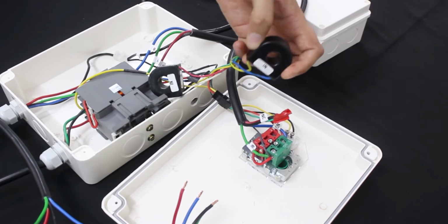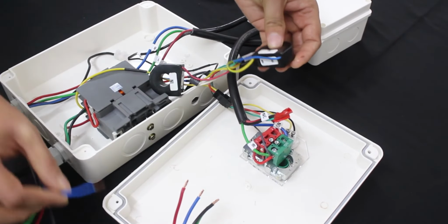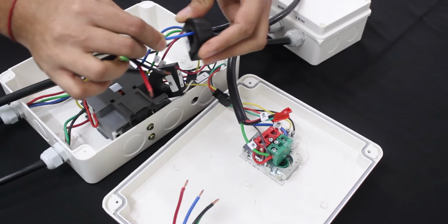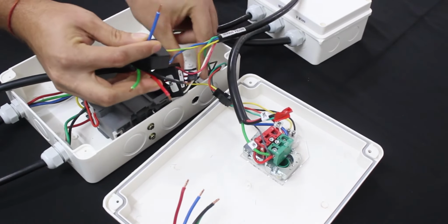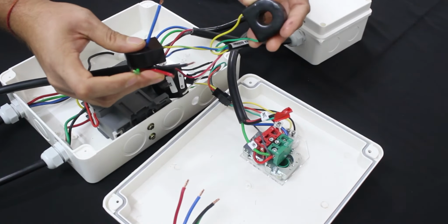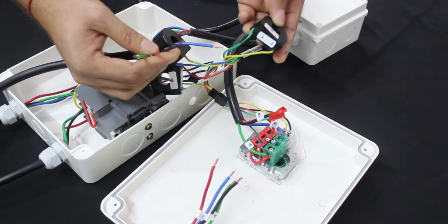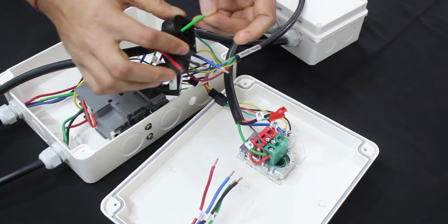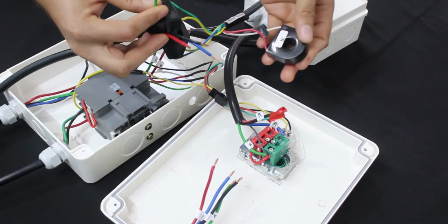Take the blue CT, BB written on the CT, and run the wire through the in section. Now do the similar for the rest of the wires. Green and red wires, RR for red and Y for green, written on the CTs.